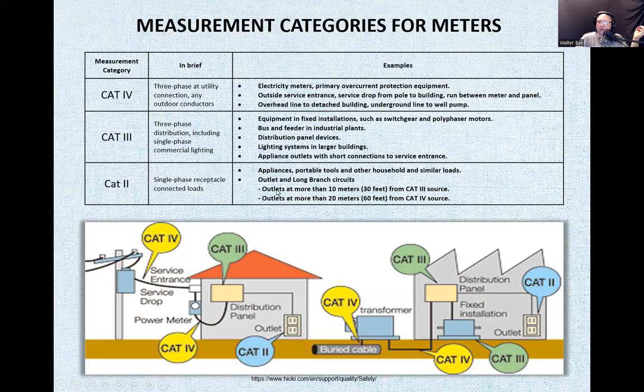Right? So this here, more than for the Cat2, you can measure things that are further than 30 feet from Cat3 source. So this outlet here will be considered you can measure that with the Cat2 meter. If it is further than 10 meters or 30 feet, that's considered a long branch. If it's closer physically to that, that becomes a short branch circuit. And then you have to up the meter. Okay. Now, let's look at Cat3.